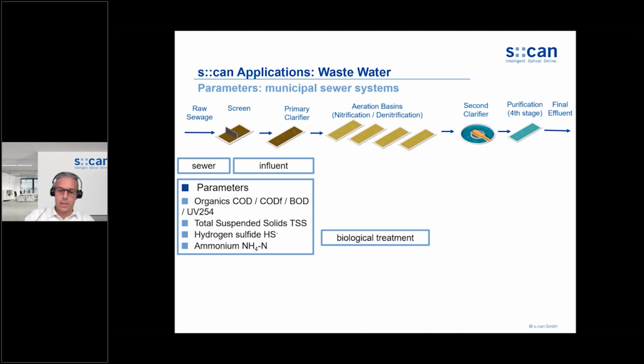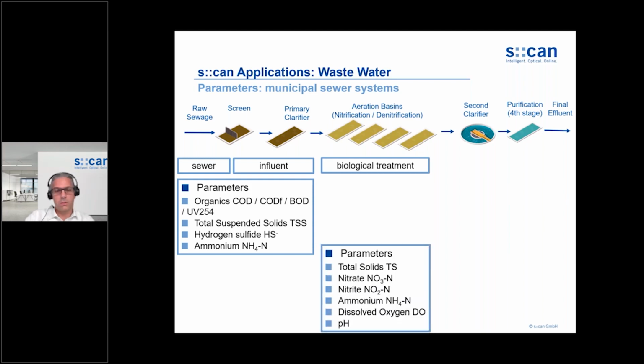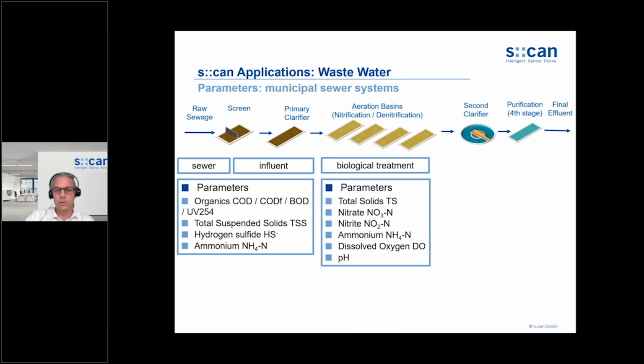The next stage is the biological treatment. In the aeration basins, the ammonium is converted into nitrate and the COD, the organics, is consumed. Typical parameters monitored here are the total solids, the nitrate, sometimes the nitrite, the ammonium, of course, the dissolved oxygen and the pH.